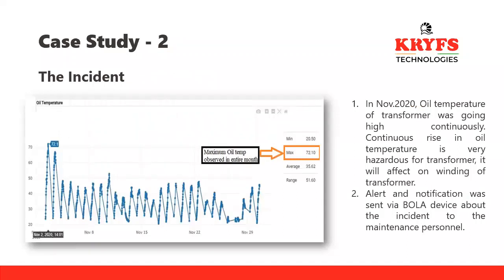During November 2020, the oil temperature of the transformer was showing continuously high. You can see the rise in the oil temperature from the graphical representation of our dashboard; the maximum it went to was 72.1 degrees Celsius, and you can see the average and minimum oil temperature as well. This alert was given to the junior engineer, and immediately it was sent via the BOLA device in the form of email notification as well as SMS alert.